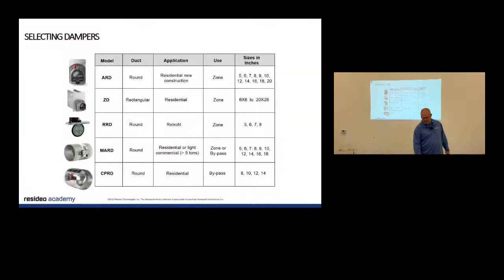The reason I'm kind of jumping through this, here we go. So we make round dampers, because some guys like to use the rounds. I've got a square duct in my basement, and they don't want to make the square duct times 2, so what they'll do is make a square and you've got the 6-inch runs. Some guys will put the damper in the 6-inch run instead of the square. It's way more expensive that way, because you're looking at probably 120, 130 bucks times every 6-inch run versus 130 or 140 bucks, maybe 200, times only 2 or 3.